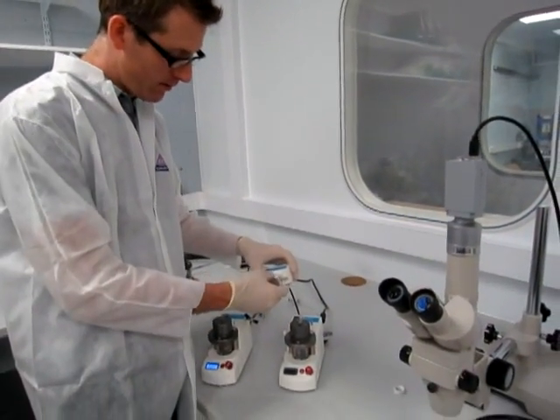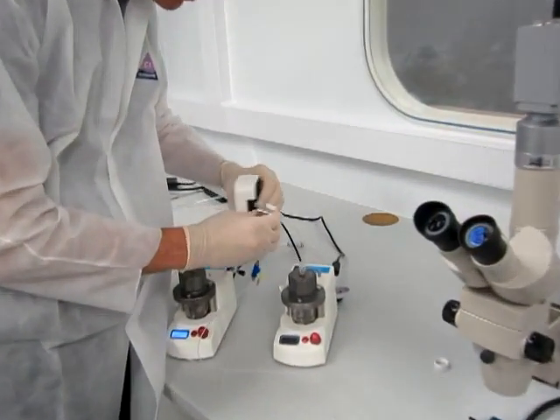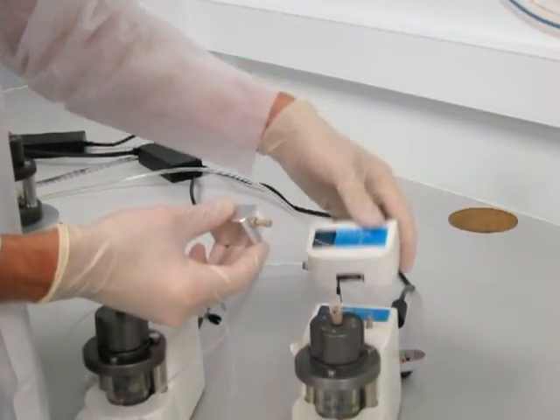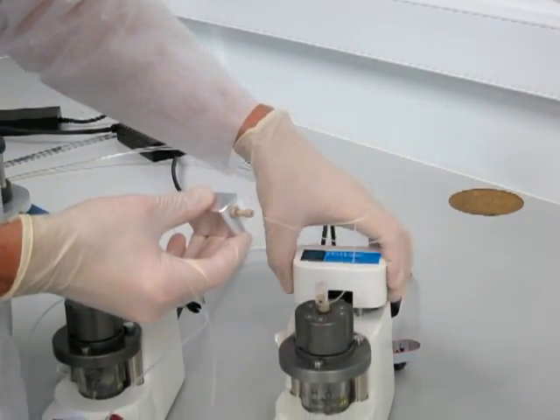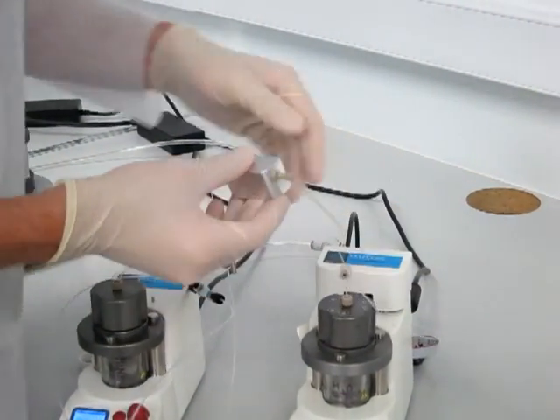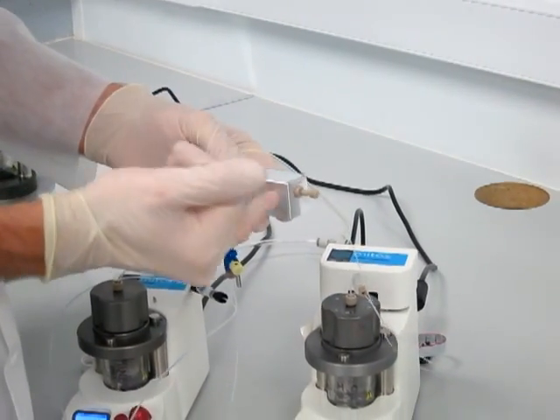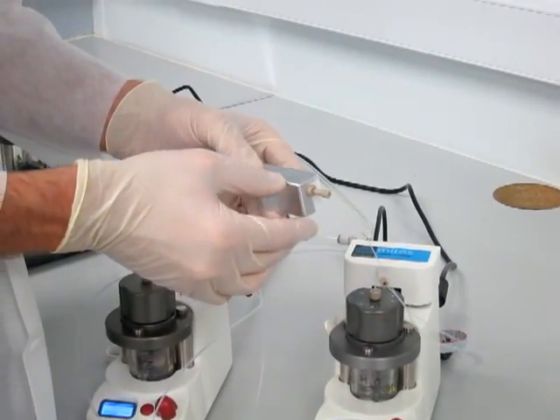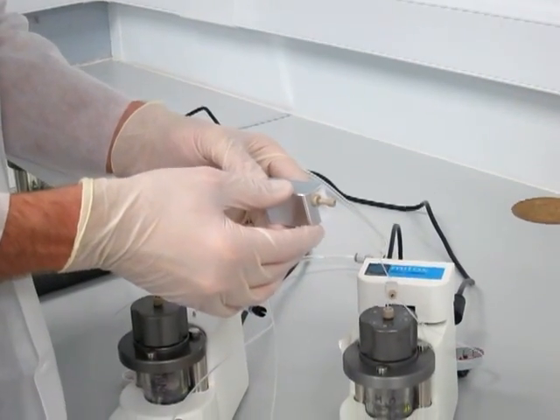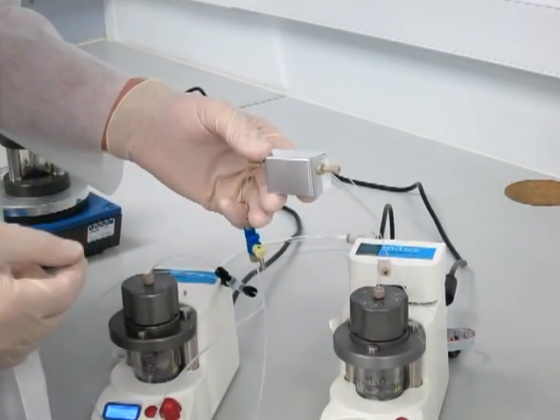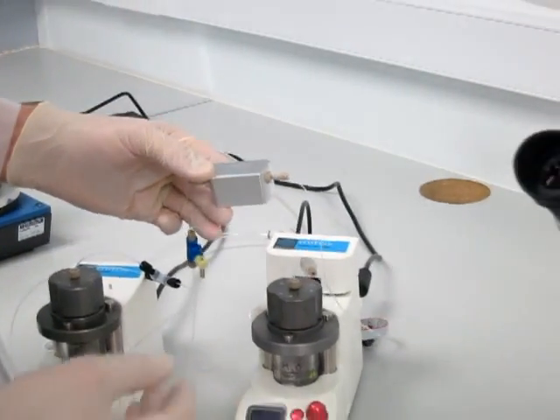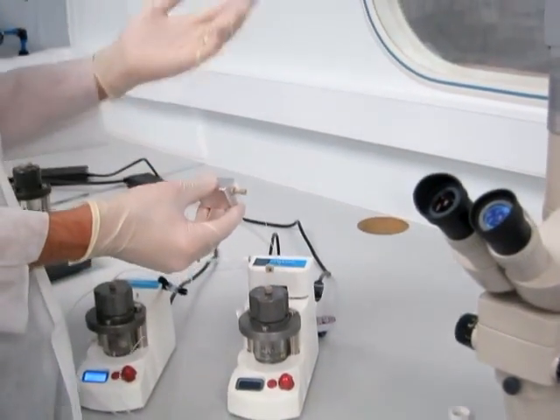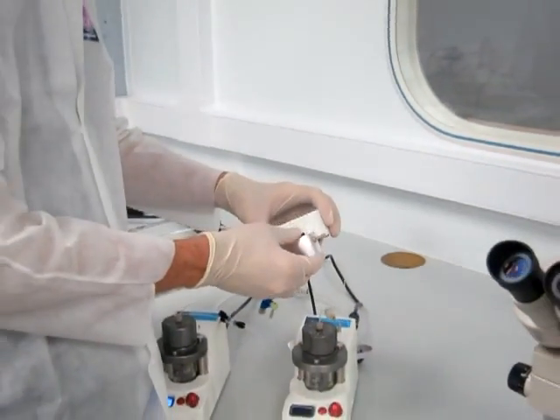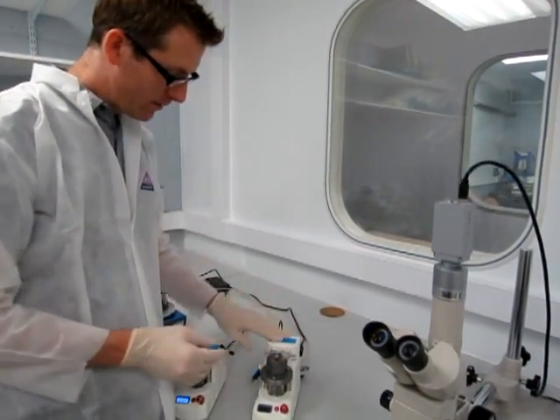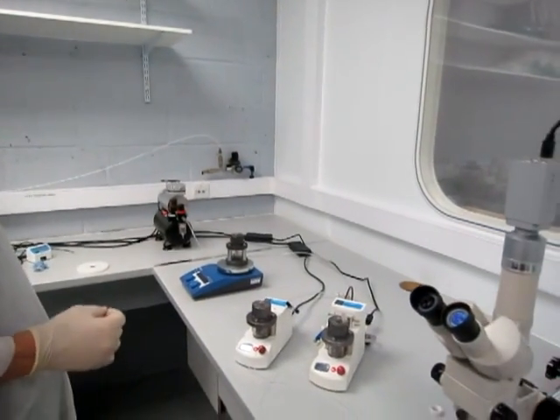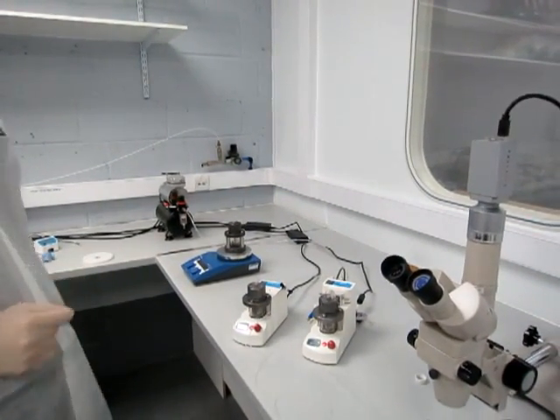And this part breaks into two parts. This is the interface, and click on that. And this is the sensor. There's a range of different sensors. This one gives you a flow rate of 1 microliter to 50 microliters per minute, which is a good general flow sensor for this type of chip. But there are other ones which have smaller flow rates and larger flow rate ranges. And that just clips into your pump. So that pretty much covers everything there.